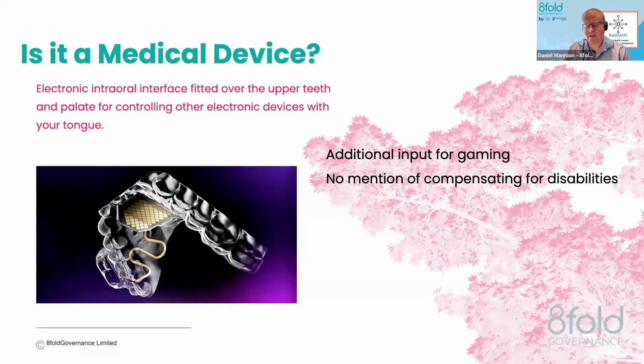The regulatory approach is the concept of an accessory. So if there's a product or a piece of software that's intended to be used only with a medical device and it has a medical purpose, then it becomes an accessory to that medical device. Accessories are considered as medical devices, and then they can be classified based on their own function. So depending on what the software is doing with the physical medical device, it might be an accessory. If it is an accessory, it becomes a medical device, but normally accessories are classified as a lower classification than the medical device itself. You also have the option of saying that the medical device plus the software is a single system, a single medical device. You regulate it as a single product.